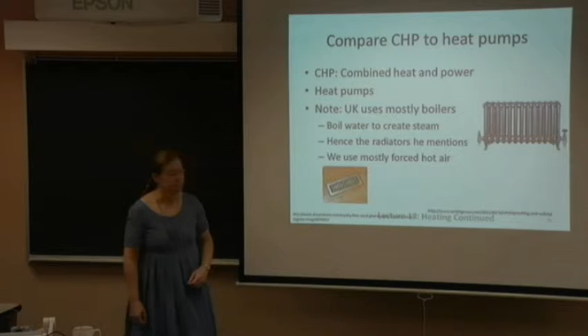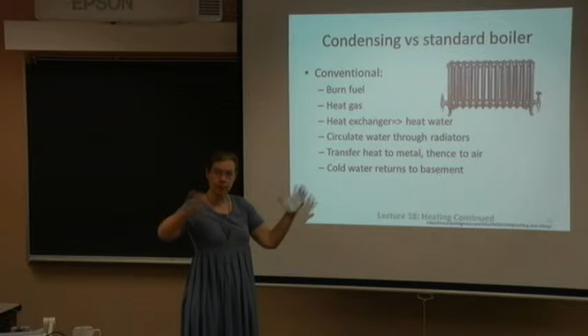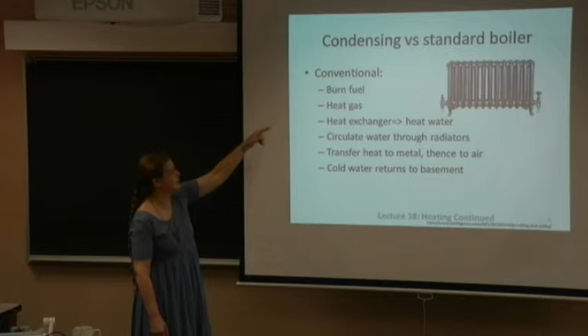Now, condensing versus a standard boiler. In a conventional boiler, you burn fuel, heat the gas, and have a heat exchanger which heats the water. So you've got the gas and a pipe full of water going through this hot gas, and the heat transfers to the water. You circulate the water through the radiators, transferring heat from the water to the metal, which radiates out to the air. What comes out is pretty cold and returns to the basement, getting heated again by burning fuel.